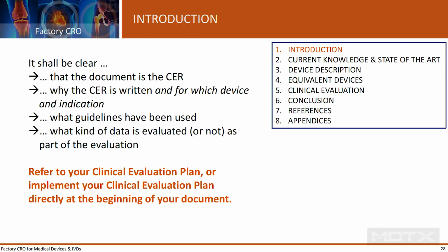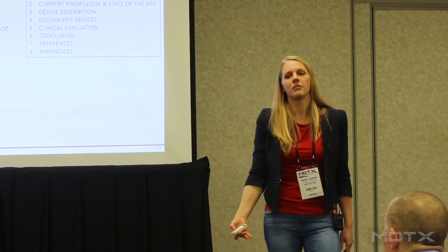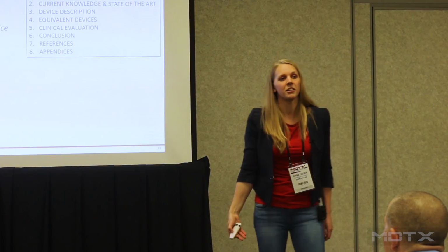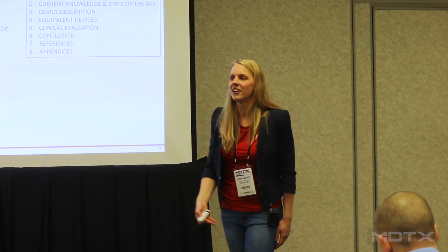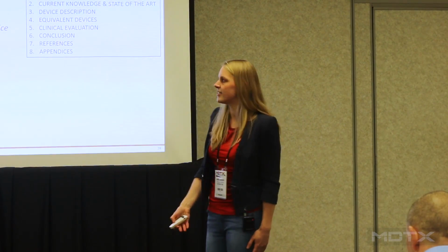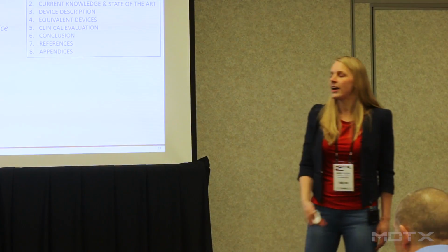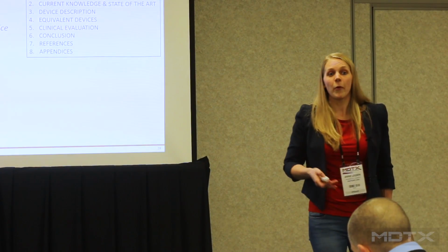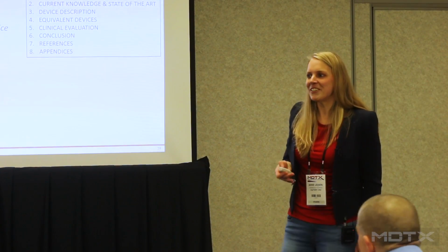So in the introduction, well, the introduction is used to set the stage. So make clear that you're writing a clinical evaluation report. Make sure that you write out for which device you're writing the report, for which indication, because as we noted before, it's not that straightforward as it seems to be. Note what guidelines have been used. The notified body will be looking for that revision 4, so make sure you mention it.